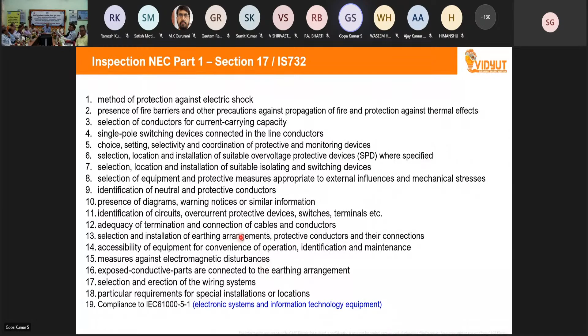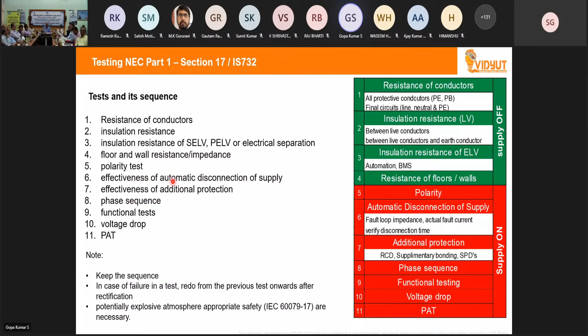There are 10 or 11 tests included in the electrical installation. For example, the fault loop impedance test, effectiveness of automatic disconnection, test number 6. With a meter, you are supposed to measure the impedance and calculate the disconnection time. Now coming to the global earthing system, this is my last slide.